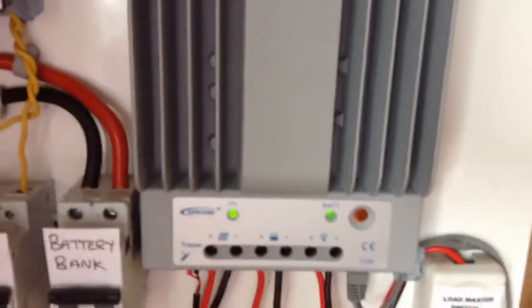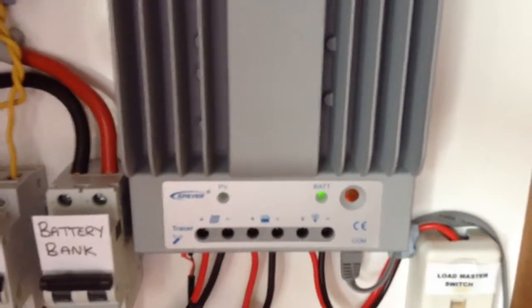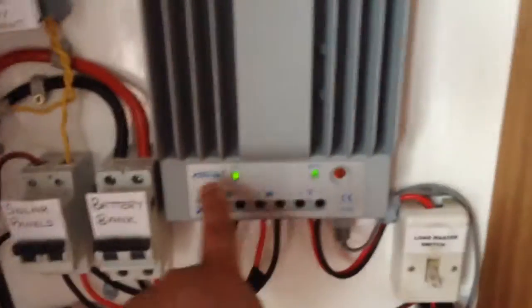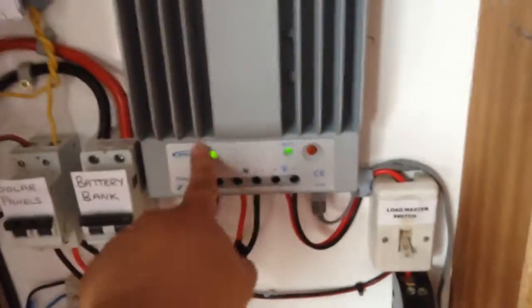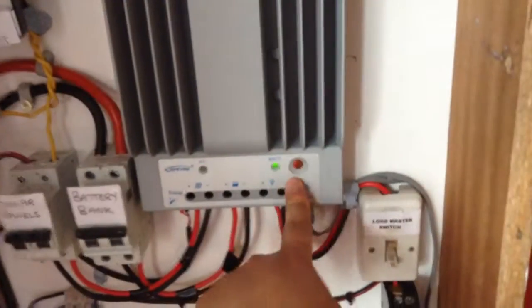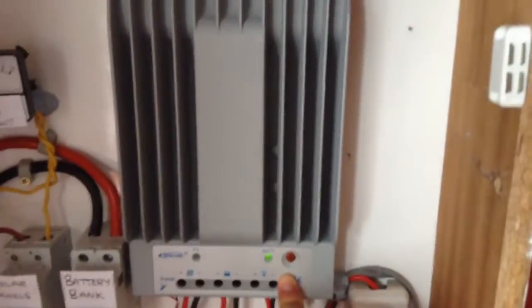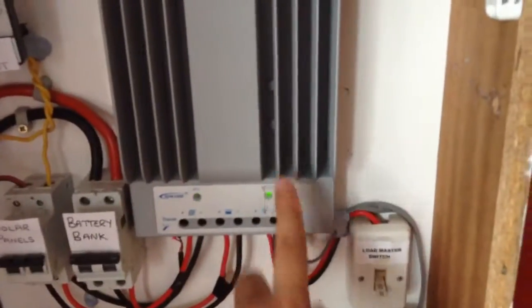The maximum input voltage of this charge controller is 150 volts, so my 60 volts is not going to be a problem. So you can have 150 volts maximum input on the input, and the load output, and I did say this is a 30 amp charge controller. It's 30 amps charging to the batteries, but only 20 amps to the output. And the 40 amp version is the same. You can only have 20 amps out of the output.